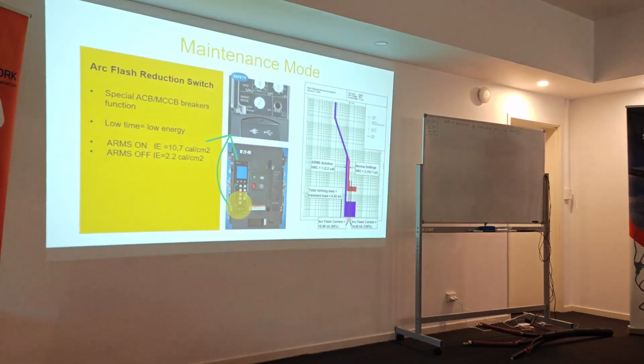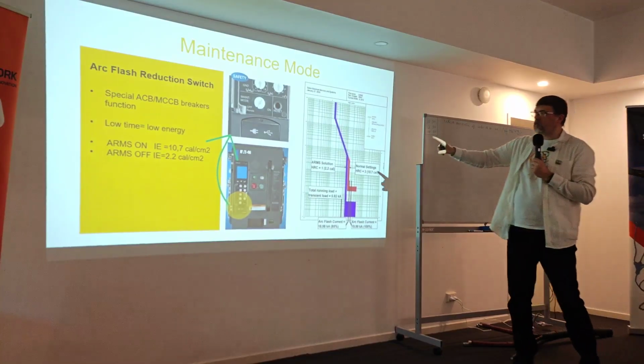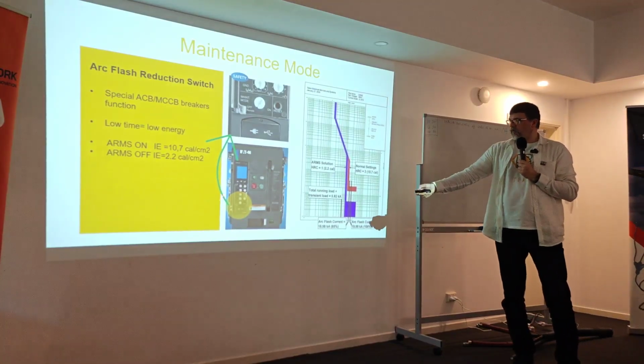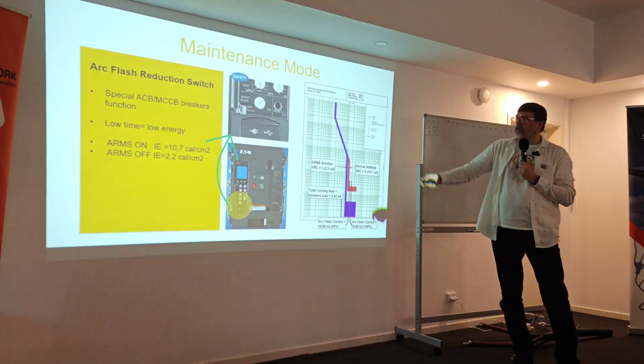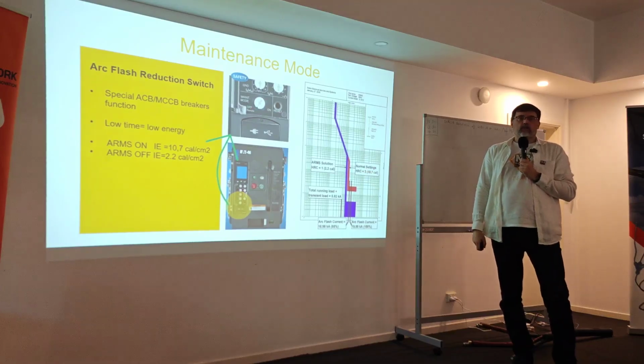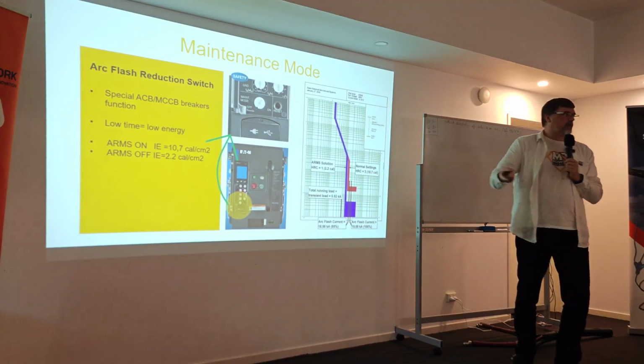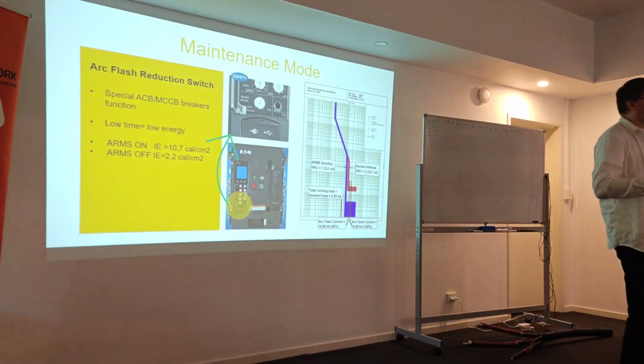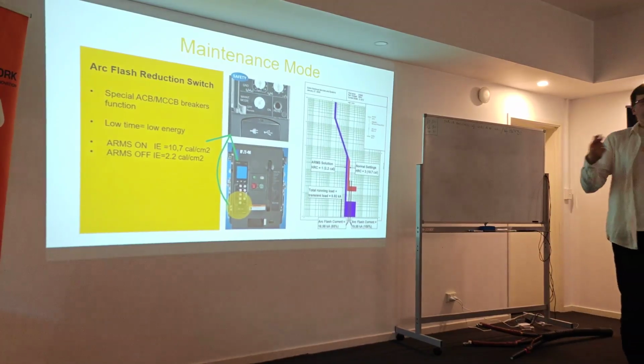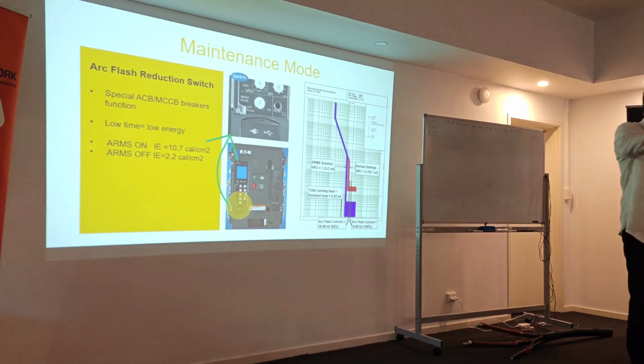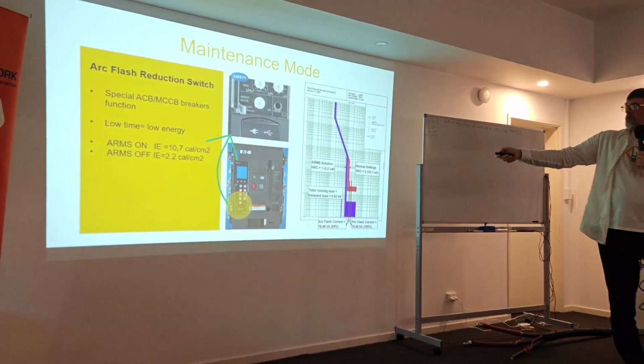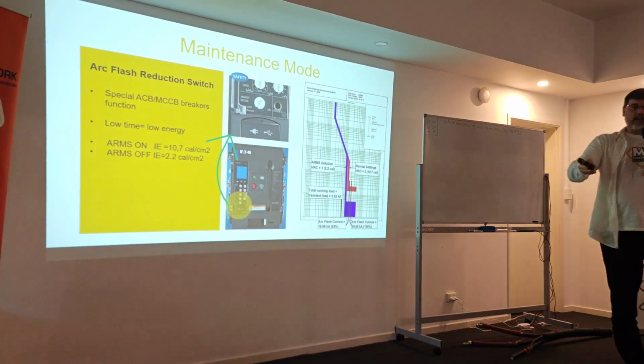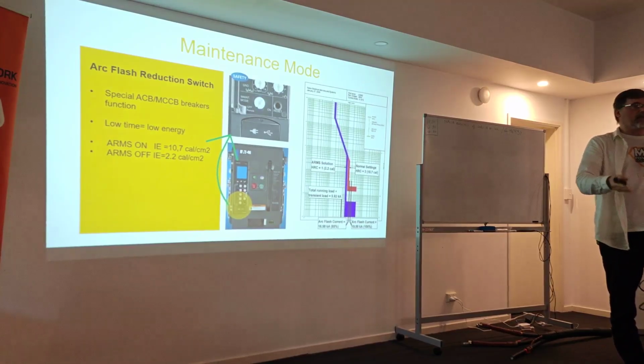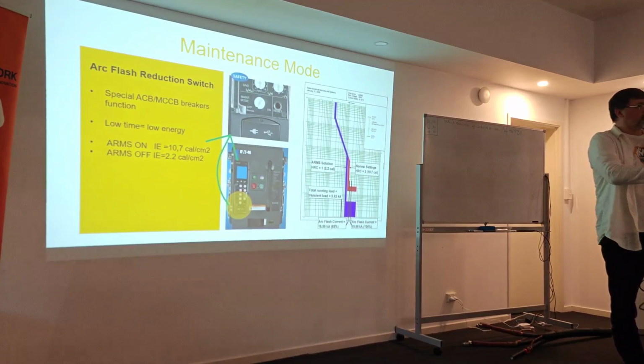So the second thing, there is something called maintenance mode, which we can do also for low voltage and medium voltage. For medium voltage it's more complicated. For low voltage this is a part of the relay, or trip unit, sorry, on the breaker. So if you buy breakers, sometimes you can retrofit the trip unit. Sometimes it depends on the breaker. Like ABB has something like an add-on for the new one, or this Ekip Touch. So if you retrofit the relay, it's like maintenance mode on-off. Technically speaking, you can do it on every breaker because you need to adjust the settings.